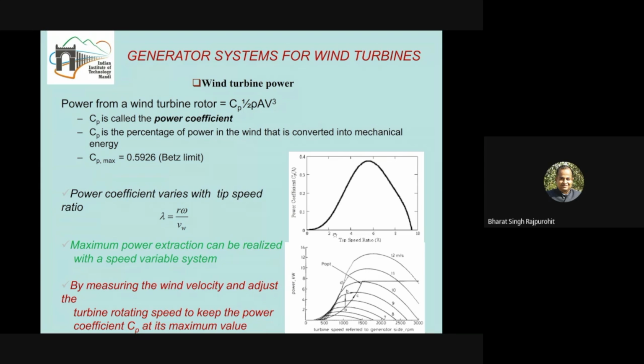Now to understand this better, let's see the right hand side below figure. What is this figure? On which relations is it drawn? This figure is between the power of a generator and, on the below side, the speed translated to the generator side, which is the generator side referred turbine speed. The speed, you can see, is varying from 500 to 3000 RPM.